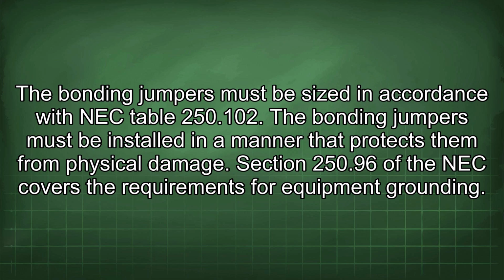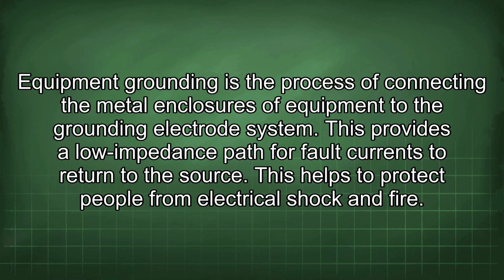The bonding jumpers must be sized in accordance with NEC Table 250.102. The bonding jumpers must be installed in a manner that protects them from physical damage. Section 250.96 of the NEC covers the requirements for equipment grounding. Equipment grounding is the process of connecting the metal enclosures of equipment to the grounding electrode system. This provides a low impedance path for fault currents to return to the source.